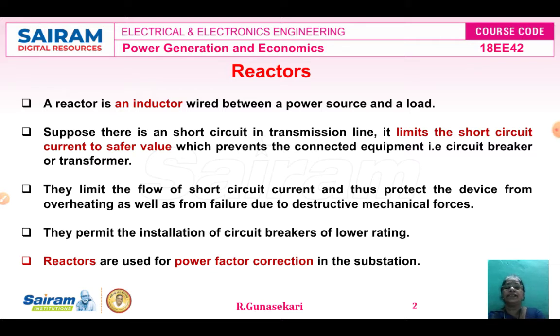The reactor is nothing but an inductor wired between the power source and a load. That means in large capacity installations, short circuit currents can attain such high values that unless certain means are used to limit them, it becomes very difficult for the installed electrical equipment to withstand such high current levels. For these purposes, auxiliary inductive devices known as reactors are used in the substation, and the reactors are introduced in each phase of the given installation.